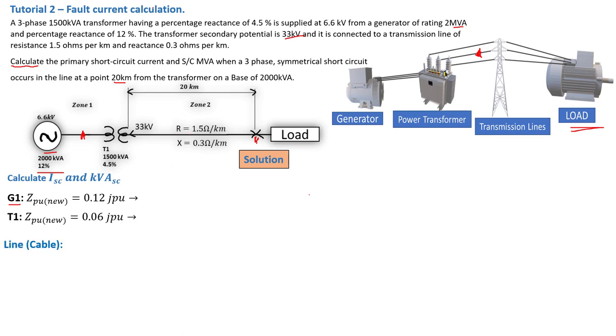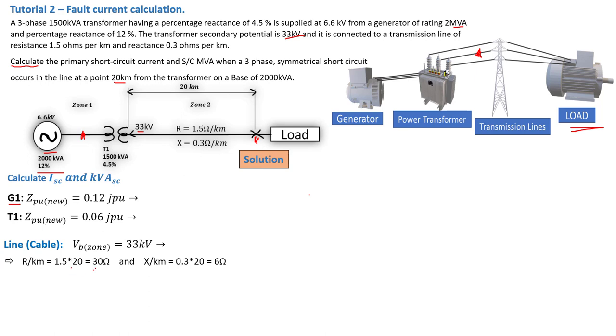The transmission line cable has a resistance of 1.5 ohm per kilometer and a reactance of 0.3 ohm per kilometer. Since the fault occurs at 20 kilometers, these values must be multiplied by 20. The zone voltage for this section is 33 kV. This gives R = 1.5 × 20 = 30 ohm, and reactance = 0.3 × 20 = 6 ohm for the 20 kilometer section.